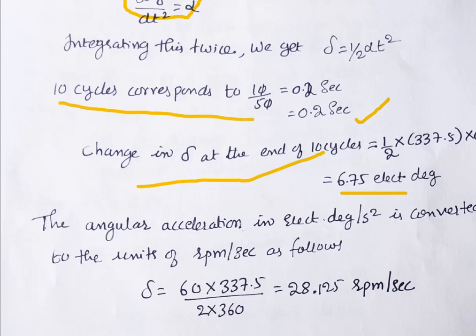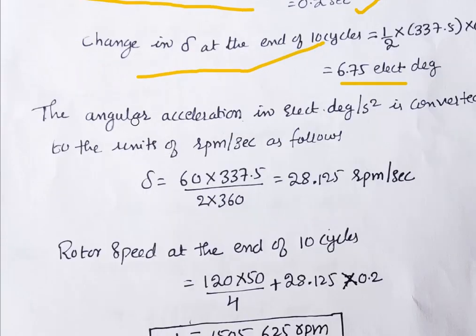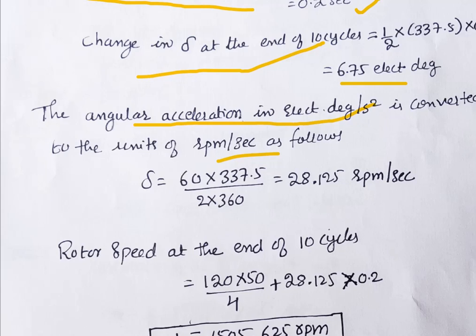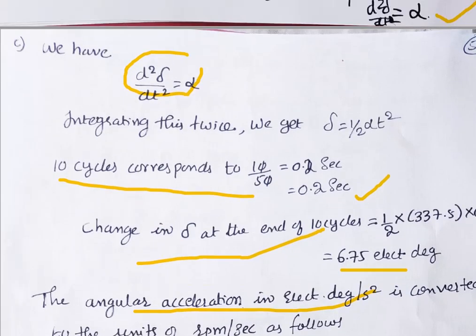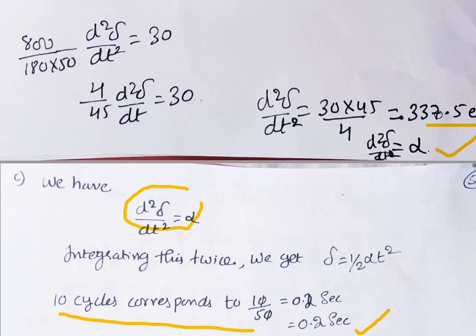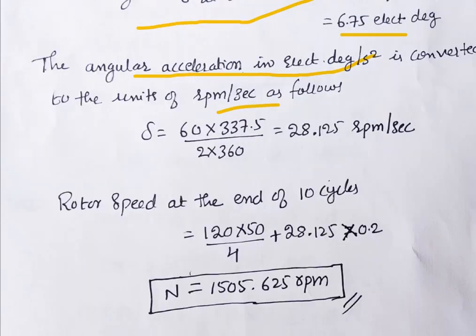To convert the angular acceleration from electrical degrees per second squared to rpm per second: Δn = 60 × 337.5 / (2 × 360) = 28.125 rpm per second. This gives the rate of speed change due to the net accelerating power.